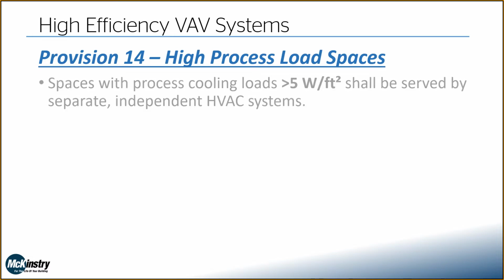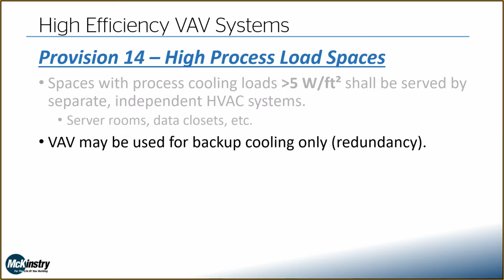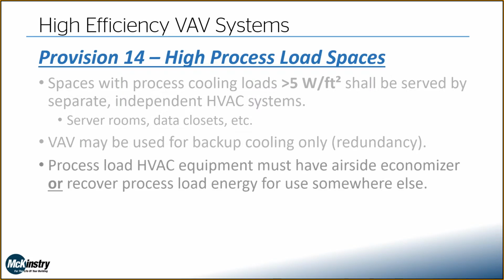High process load spaces. So if we have any spaces with process cooling loads greater than 5 watts per square foot, which is a decently high value, these have to be served by separate and independent HVAC systems. So the typical application here would be server rooms and data closets. We may use the VAV system for backup cooling only to offer some redundancy, so if that separate independent system goes down, they can still cool that space. Additionally, that process load HVAC equipment has to have an airside economizer, or you need to recover that process load energy to use somewhere else. You need to recover that heat.